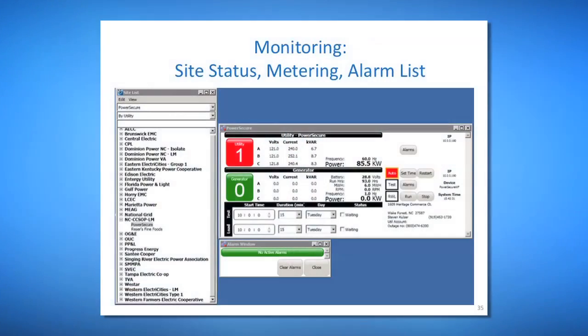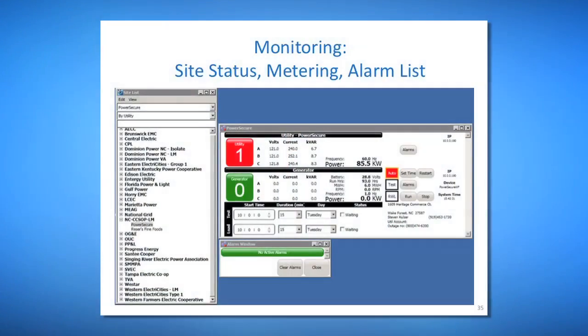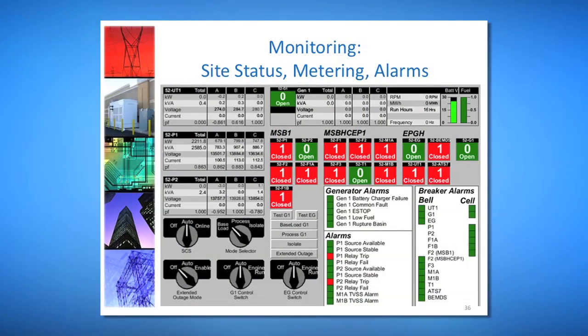On a global metering and monitoring screen, we can see the status of the two circuit breakers, which one's closed, utility or generator, or both, and get a bird's eye snapshot of volts and amps per phase, plus the beginning of the master alarm list. If everything's fine, that's as far as you need to look. You can drill down further for more operational data, switch status, and a nice HMI to view it all.